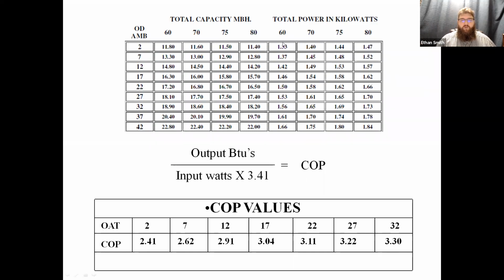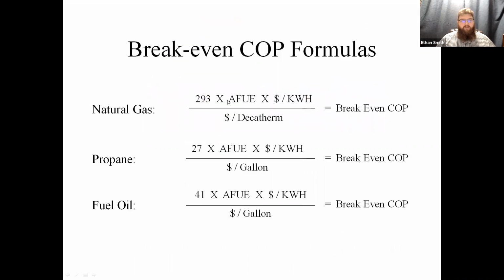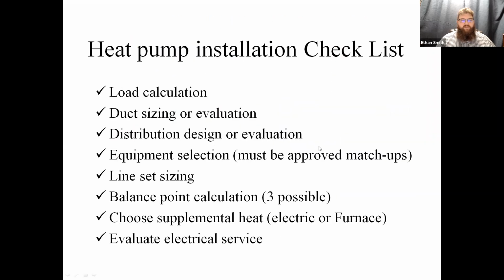It's all going to depend on what your utility rates are year to year versus the performance of your particular unit. So be aware of that. One of the things that I do differently on mine is I actually do not use the published AFUE. I actually do a combustion analysis on my particular installation, because that's going to be a lot more accurate than the testing they did in Florida. So that's the break-even COP. Any questions, guys?